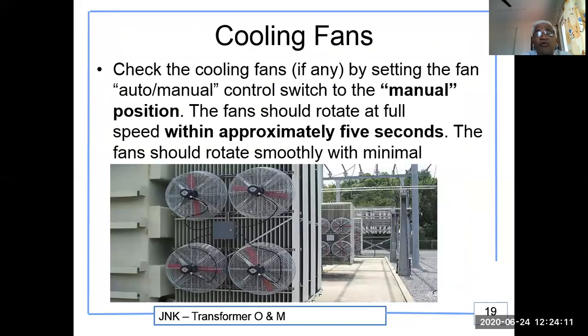Cooling fans. Check the cooling fans, if any, by setting the fan auto and manual control switch to manual position. The fans should rotate at full speed within approximately 5 seconds. The fans should rotate smoothly with minimal noise.